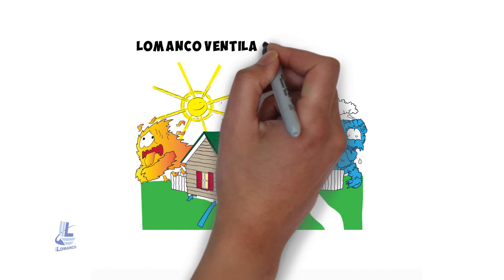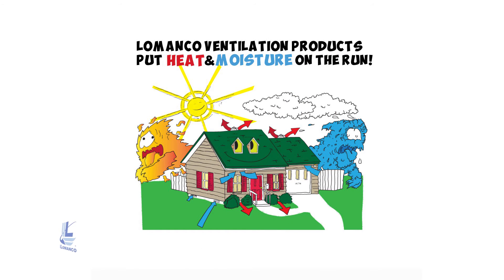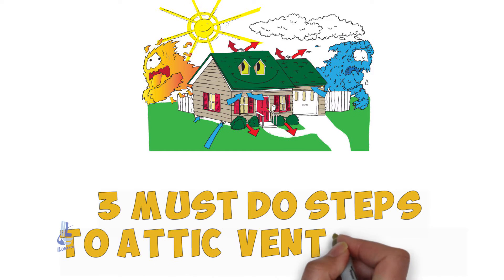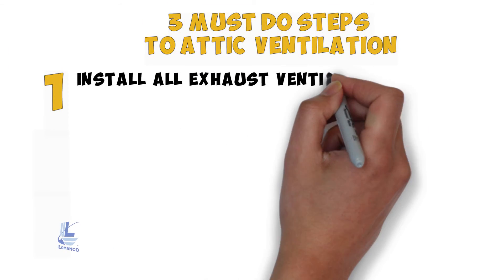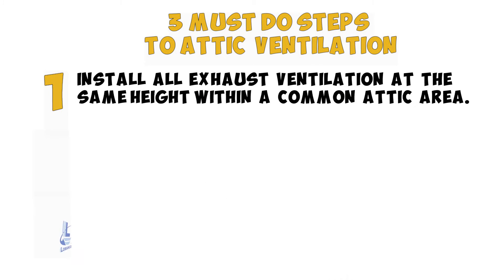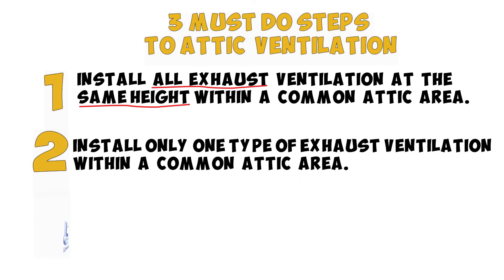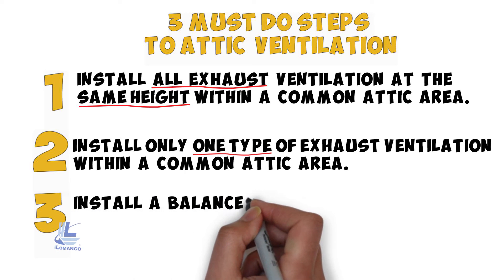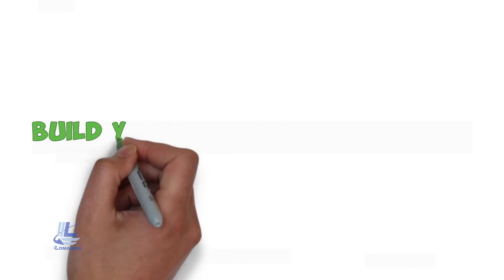Lomanco ventilation products put heat and moisture on the run. The three must-do steps to attic ventilation: Step one — install all exhaust ventilation at the same height within a common attic area. Step two — install only one type of exhaust ventilation within a common attic area. Step three — install a balanced system of exhaust and intake ventilation. Now that you know the three must-do steps to attic ventilation, we can build your ventilation system.